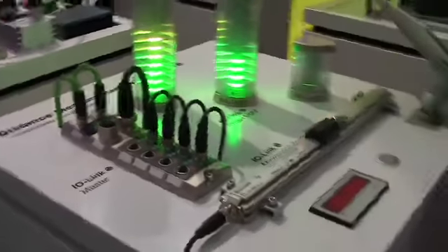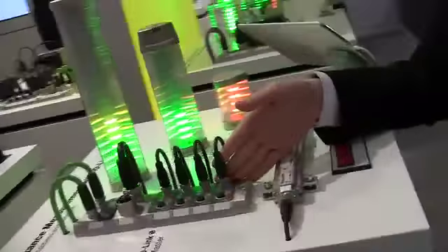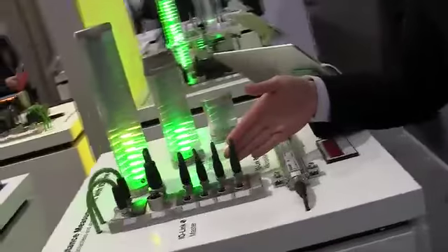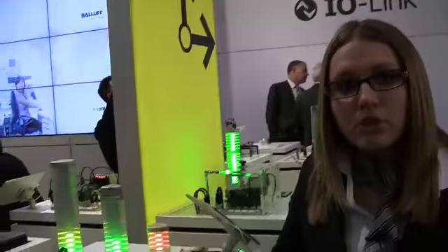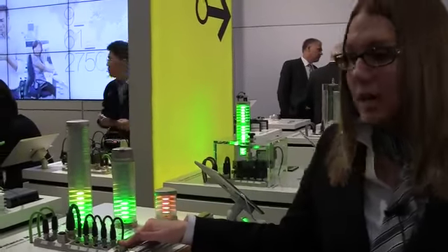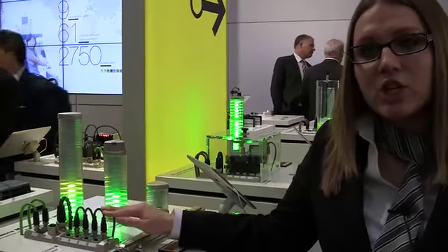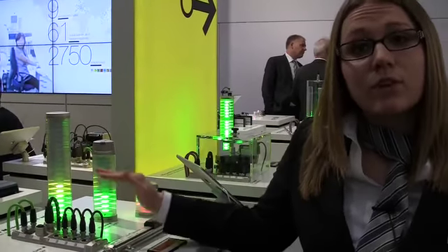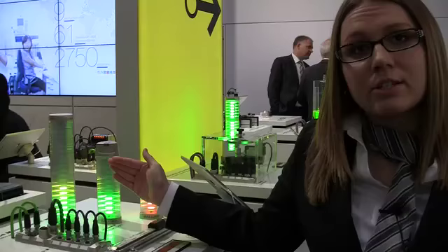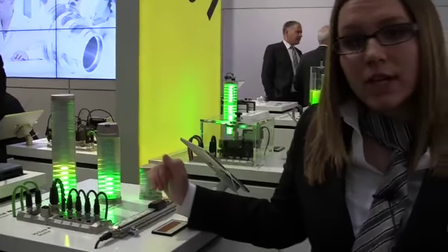The nice thing about IO-Link is, within this block, we have one IP address, and we have all of our devices on this. IO-Link is a great platform to use because it provides some enhanced troubleshooting as we're working through our system and our process, and we're constantly sending information up to the PLC and even further up into the cloud, into our ERP system, to give us some diagnostic information ahead of time.